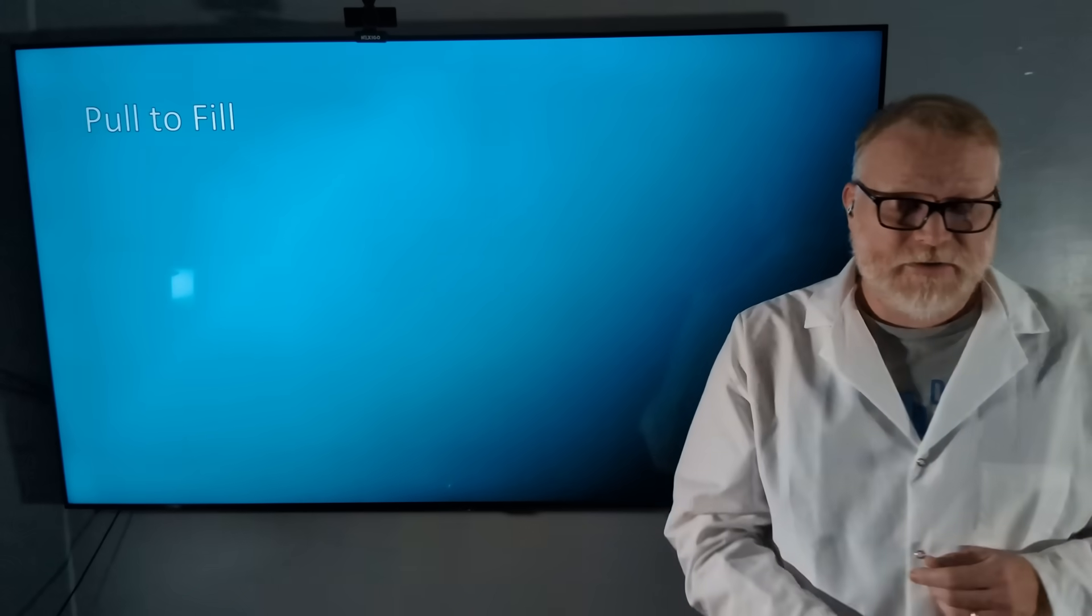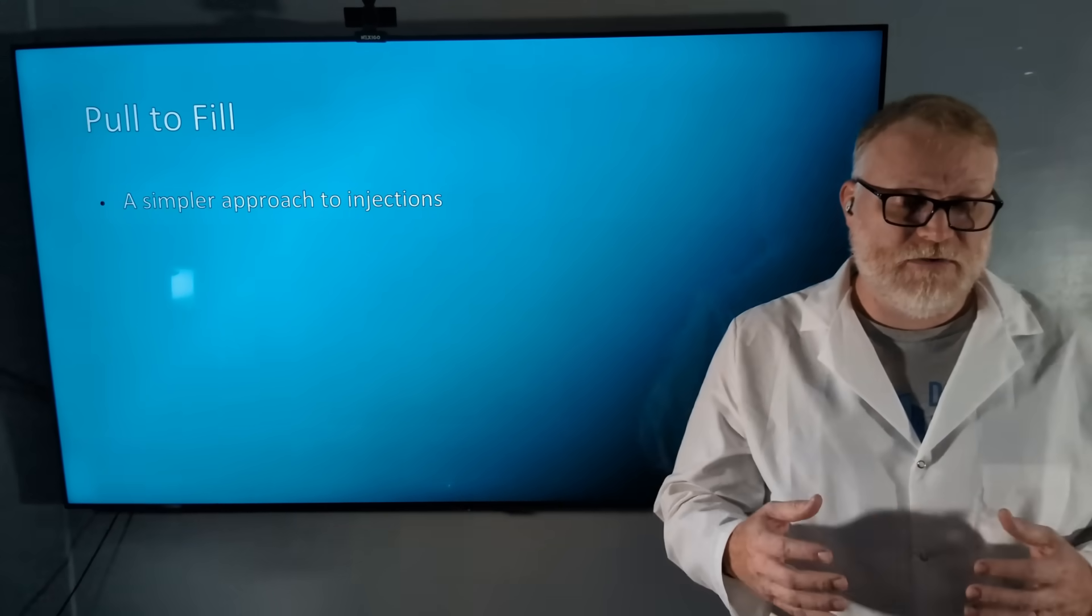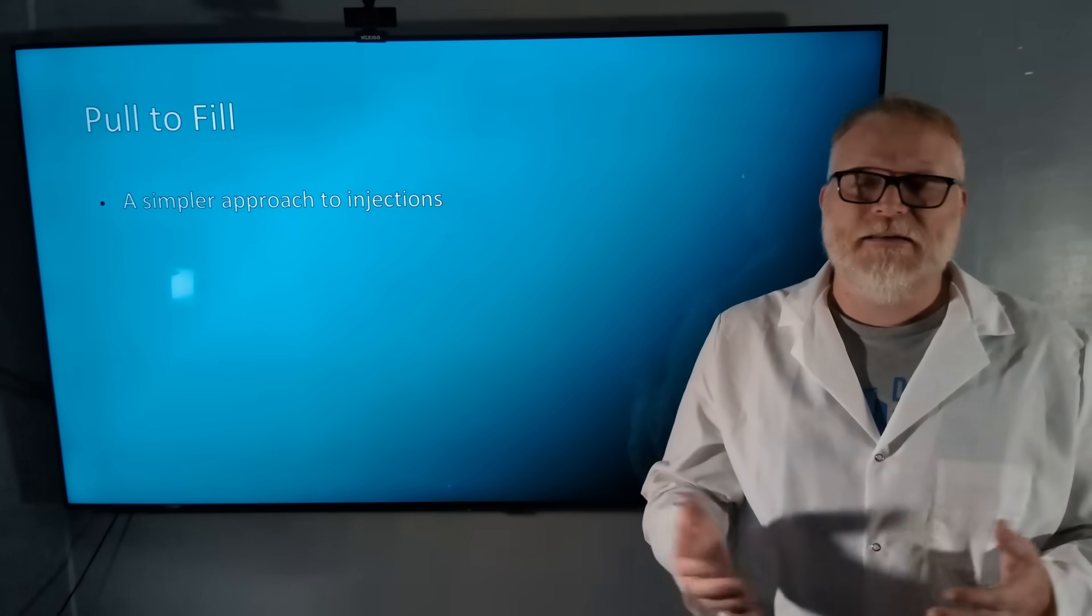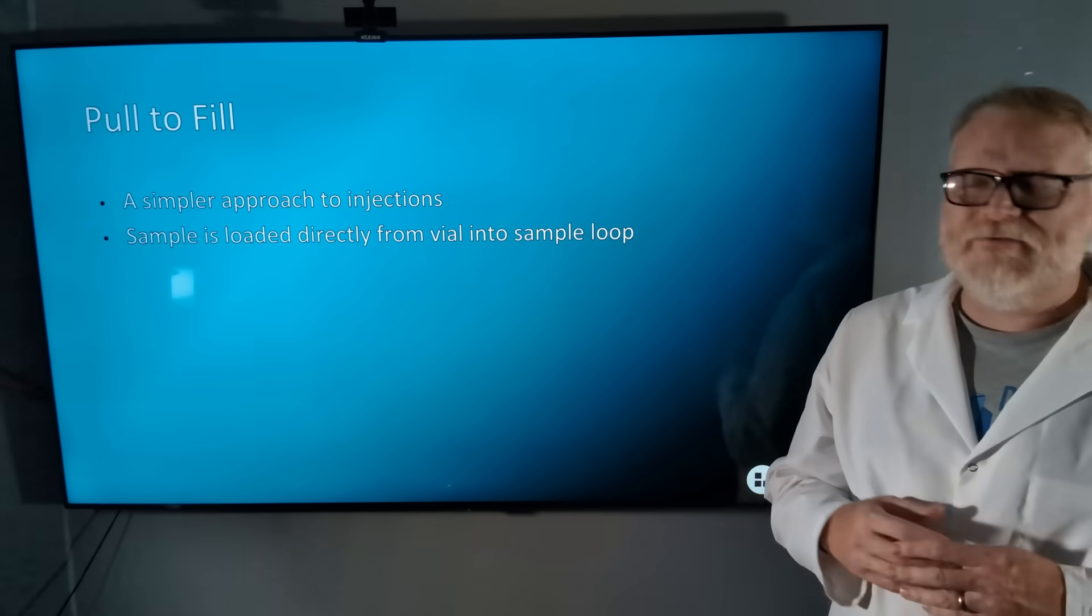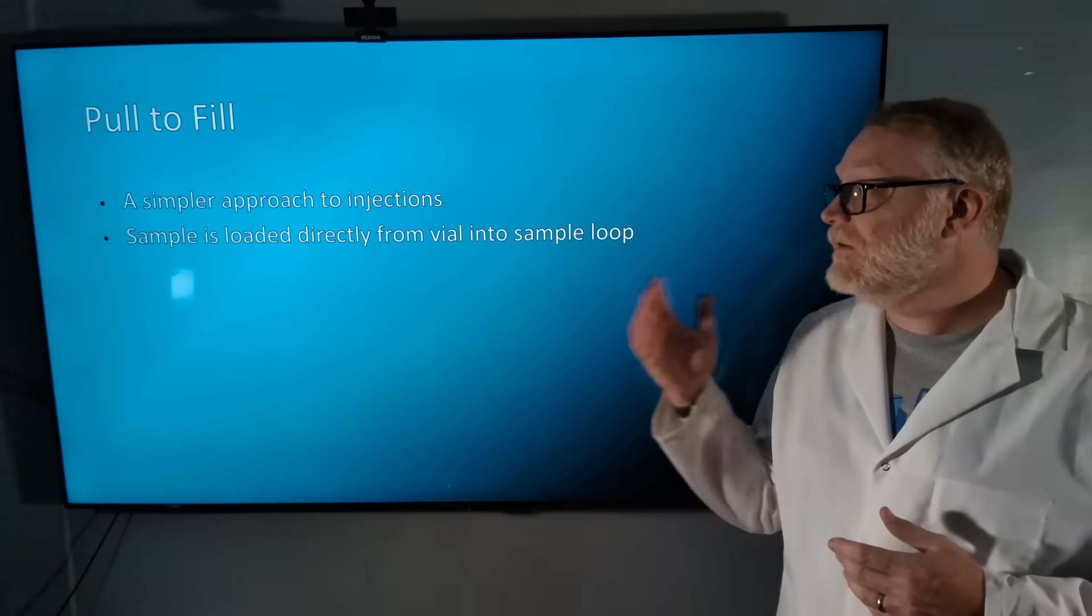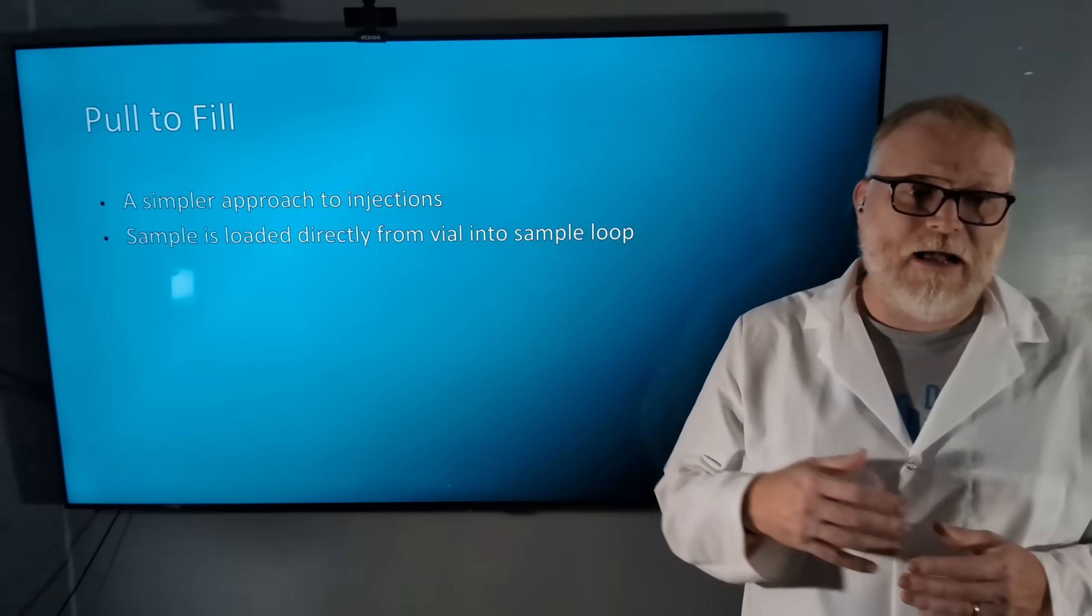The next is pull-to-fill. Pull-to-fill is a much simpler approach to HPLC injections. A simpler HPLC means less moving parts, means less things can break. This style does use a fixed loop, and the sample is loaded directly from the vial onto that loop.